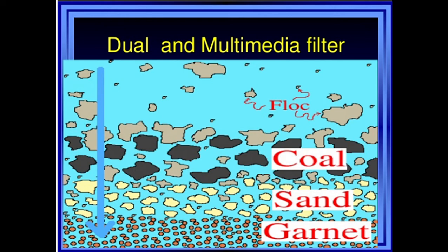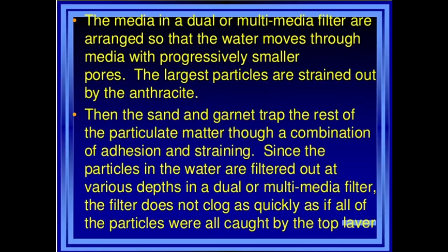The second topic is the dual and multimedia filter. The diagram shows various filter media — anthracite, sand, and garnet — that may be used in a dual and multimedia filter. The media in a dual or multimedia filter are arranged so that the water moves through media with progressively smaller pore size, filtering out larger particles first.